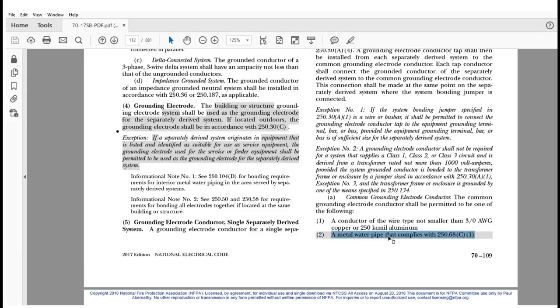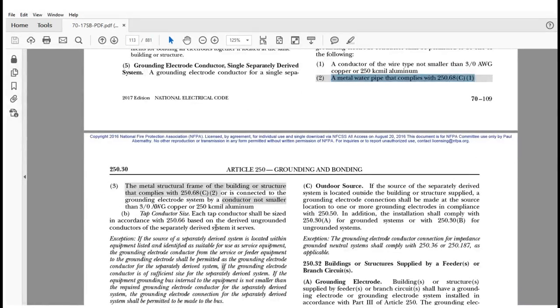Now this came in 2014, so this isn't necessarily a new change for that aspect of it. And then again, the metal structural frame of a building or structure that complies with 250.68(C)(2) or is connected to the grounding electrode system by a conductor not smaller than 3/0. So that portion of it did not change. Okay, it just added a little bit of a better list to it and added that water pipe in there as a viable means provided it meets the requirements of 250.68(C)(1). All right.